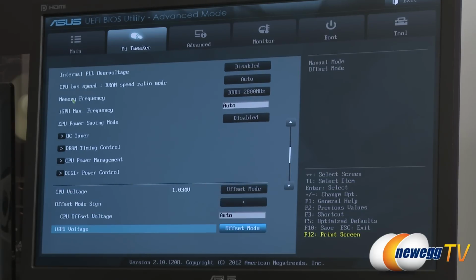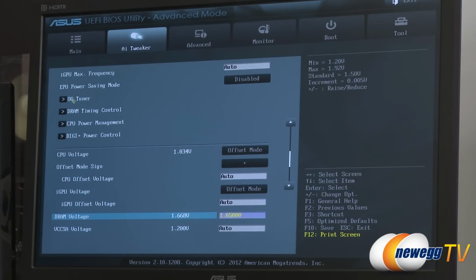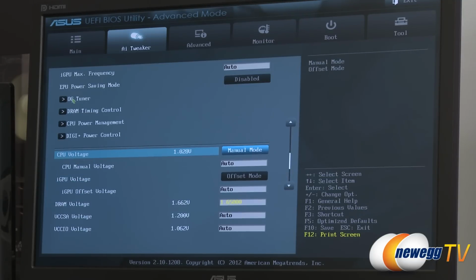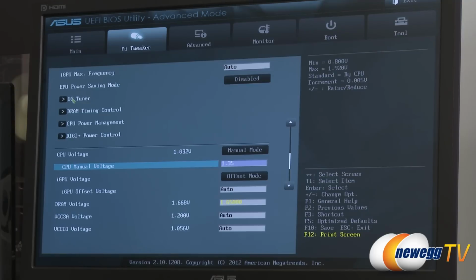We want to go ahead and make an adjustment in terms of voltage. We discussed using an offset versus a manual voltage. If I select manual and manually define my maximum, let's say 1.35, we're going to let you know that it's already starting to get into the caution area of being a dangerous voltage level. I think overall we're going to be okay, but keep in mind that with a manual voltage, it's going to keep that same exact voltage whether you're at the idle frequency or at the peak frequency.